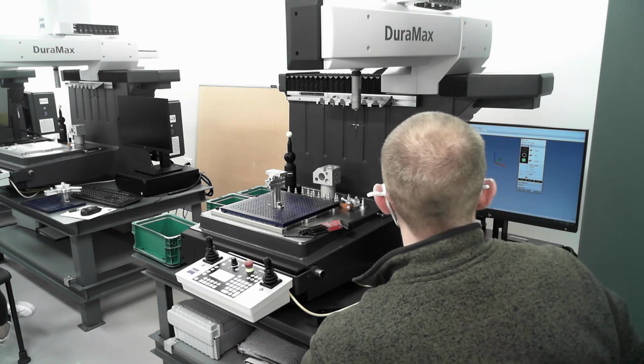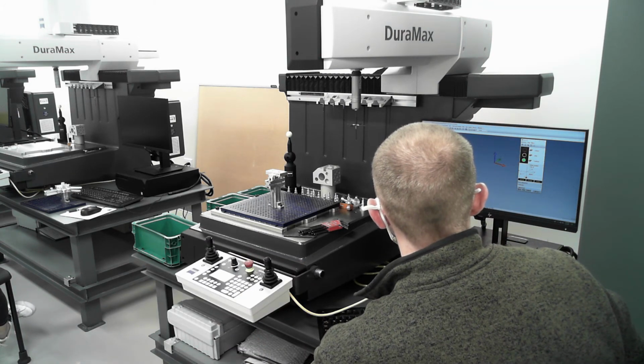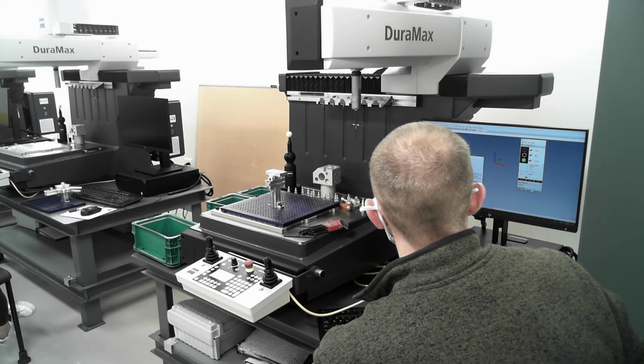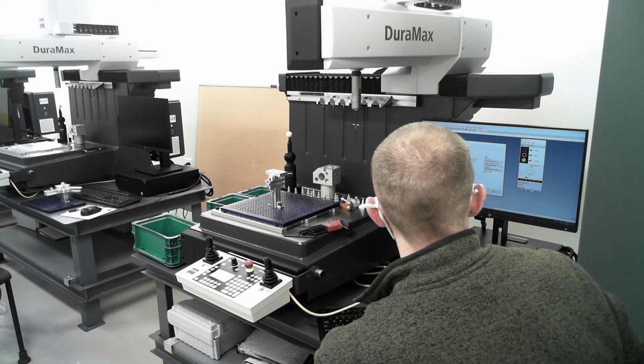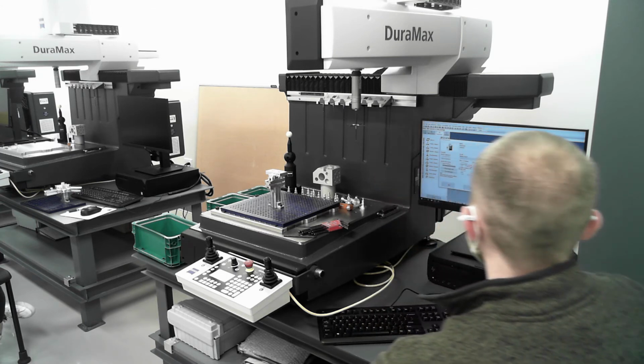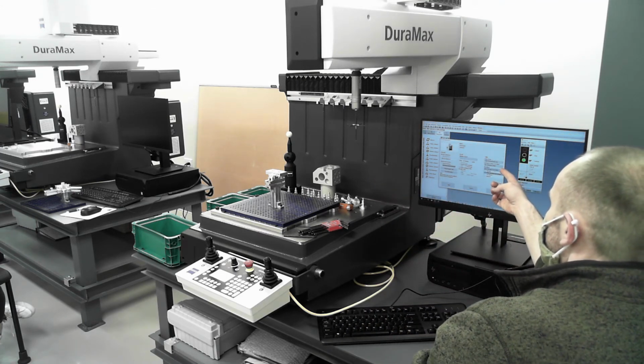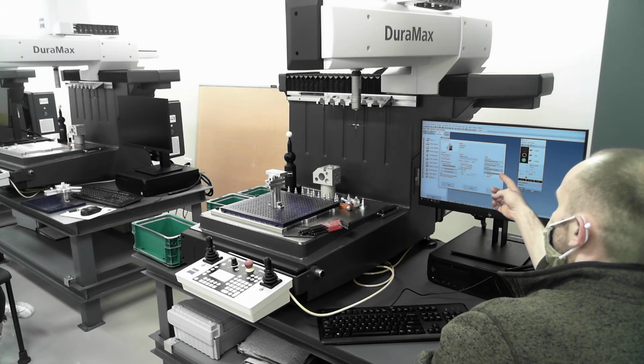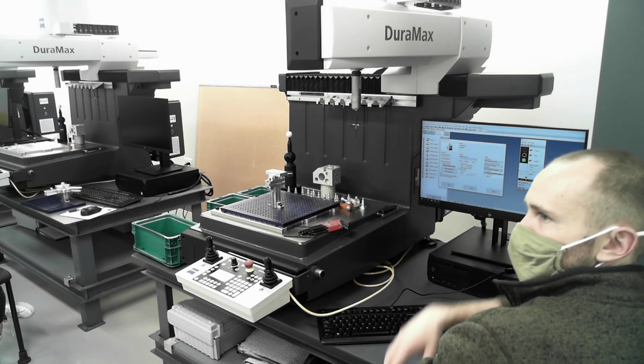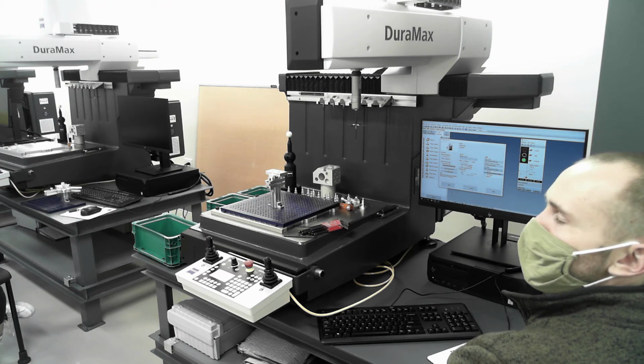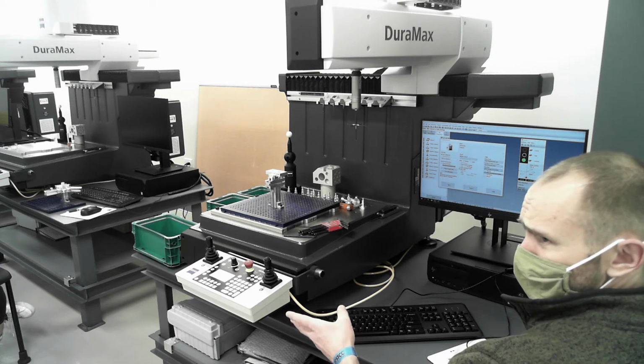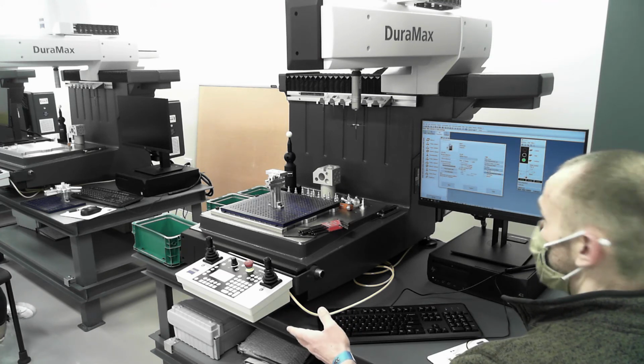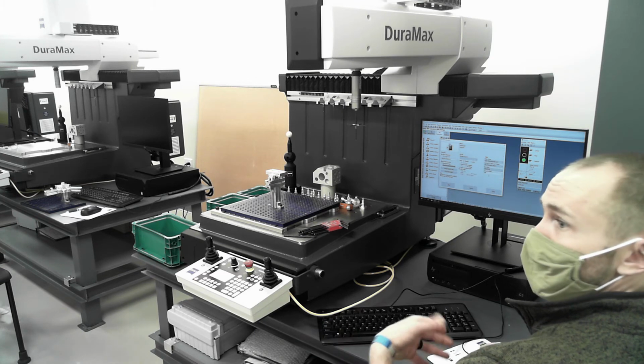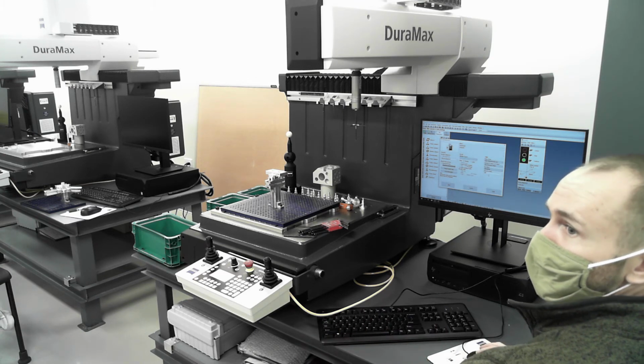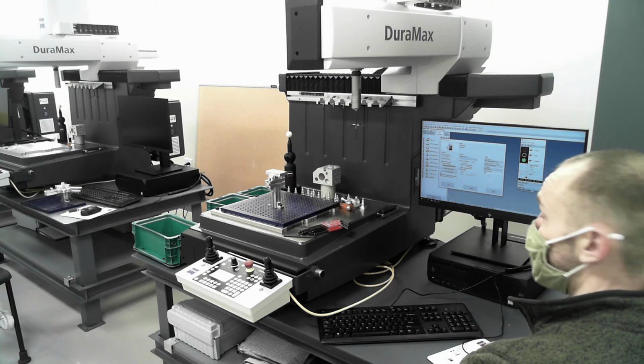So we have probe number 1 active, and we are now going to come over to our characteristic menu and hit run. We said we wanted to do clear existing results and manual alignment. What do we want to do for our run mode? We want to do normal, slow through first feature, step mode. Slow to first feature, that's what we want to do if we already know what's happening. But do we know this is going to happen correctly? No, so we want to do step mode. And step mode is the equivalent of a dry run. So I would put that in your notes. Step mode is the equivalent of a dry run.